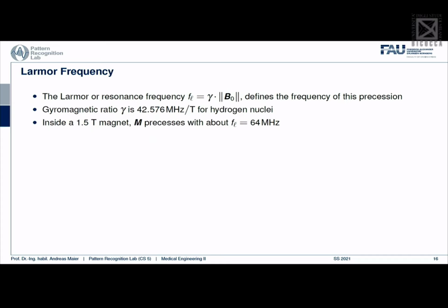And the FM radio that we used to have in our cars before the DAB system was 100 megahertz. So we're talking about the same wavelength and the same frequencies as FM radio, just to give you an idea. Which, by the way, given that you don't only have FM radio in the air, but lots of other things, the MRI scanner has to be built in shielded rooms, shielded from every single possible source of electromagnetic interference.